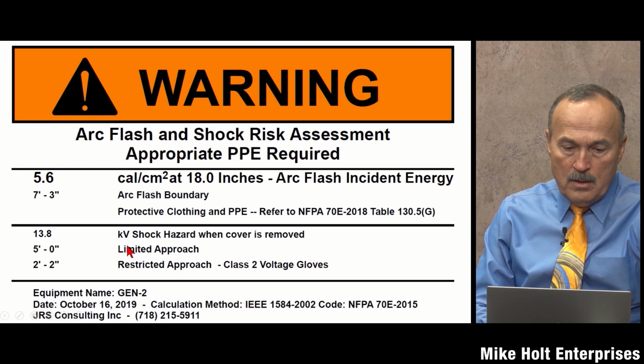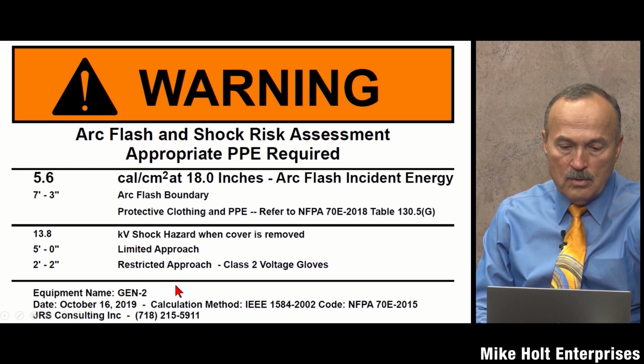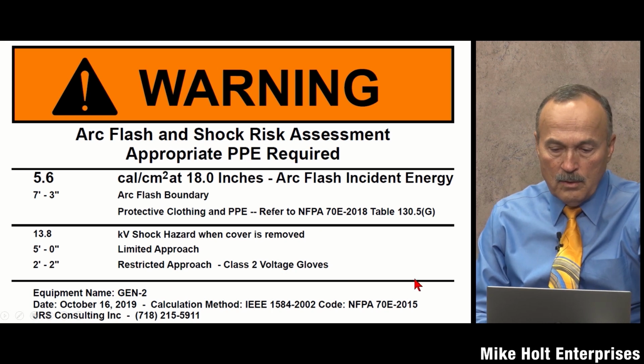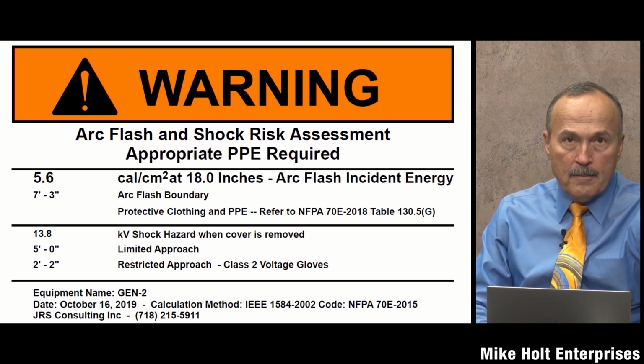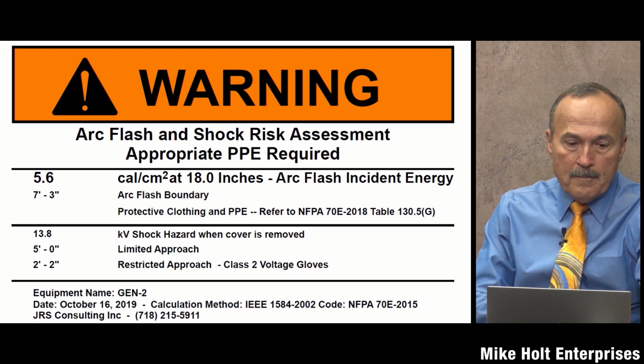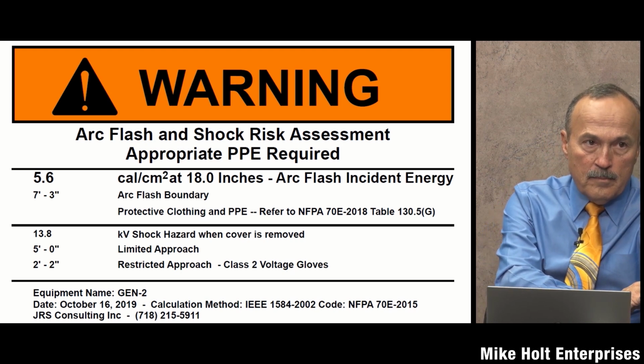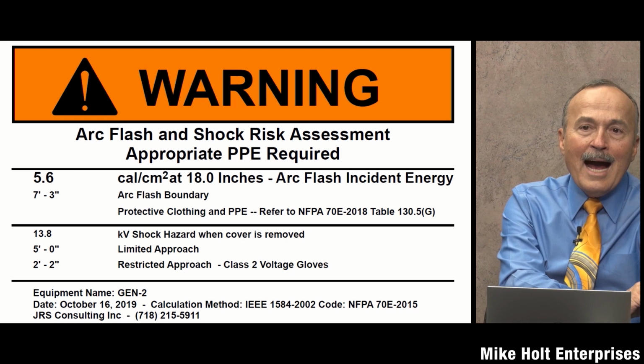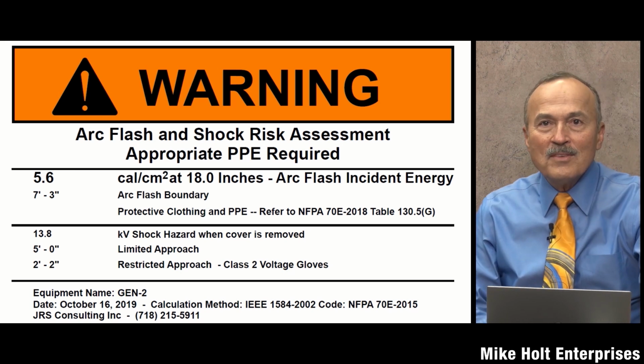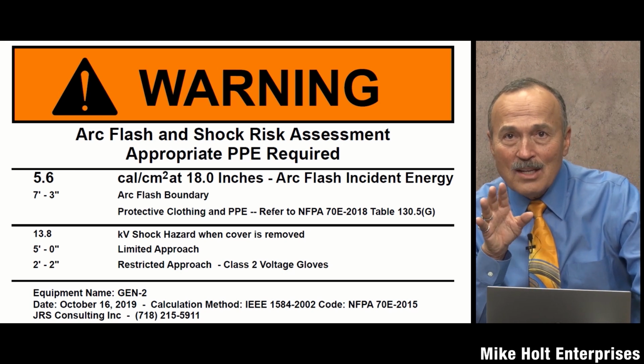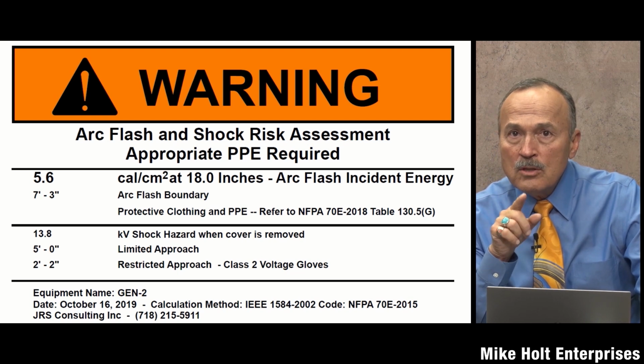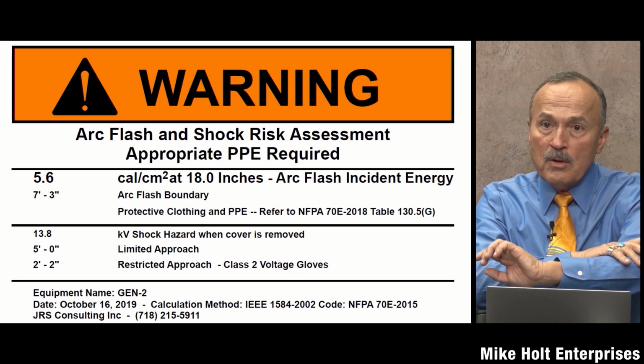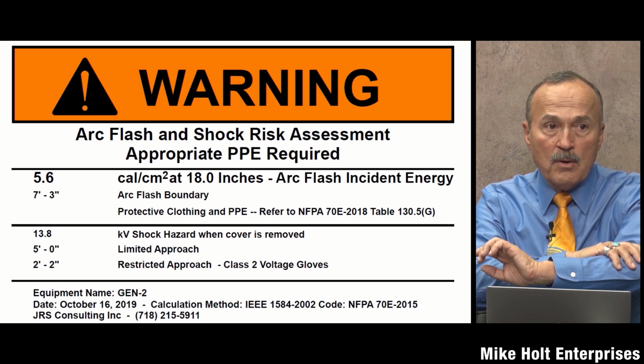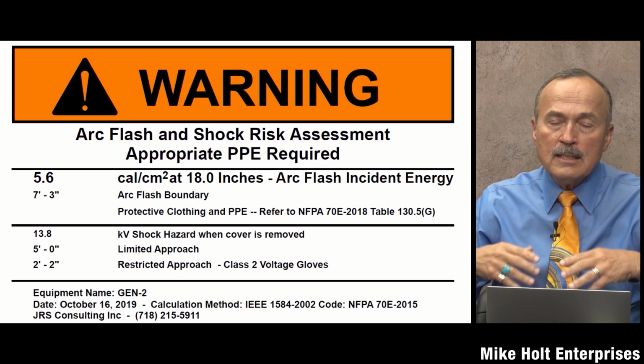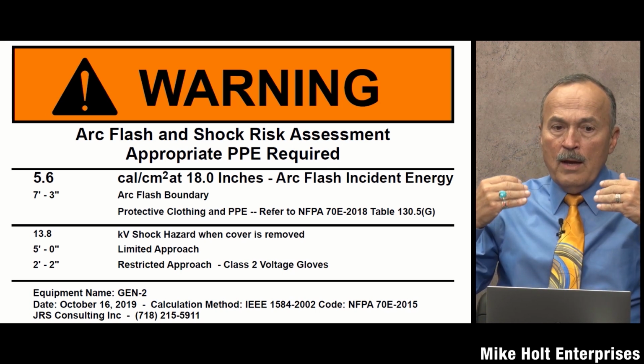Then, this is 13,000, which is why this value is so high. Okay, so this is a 13,000 volt system. Okay, we're not getting further there. Mike, another way of looking at that is that the arc flash boundary is where it is at 1.2 calories per square centimeter. Ah, that's right. That's not in 70E, and we're not getting into that, but 1.2 calories is when you go to a third degree burn? Second degree burn. You're right, of course. It's a second degree burn at 1.2 calories.